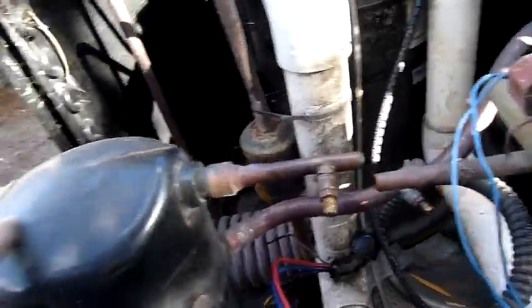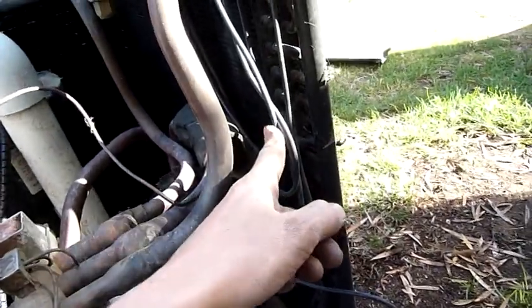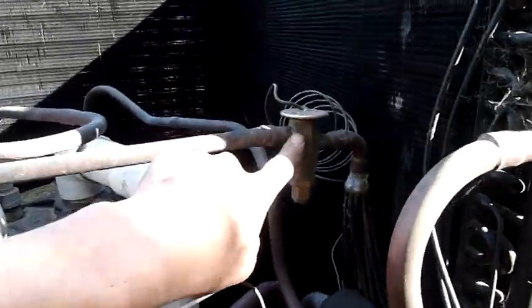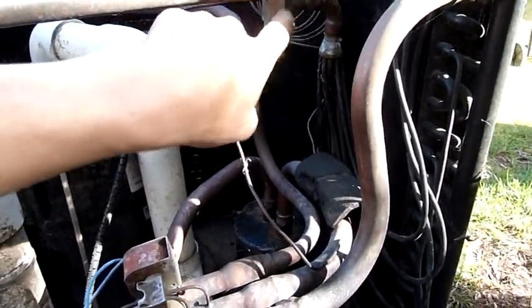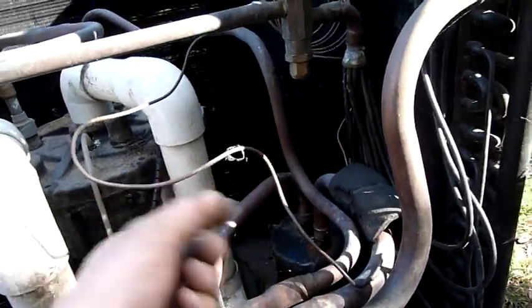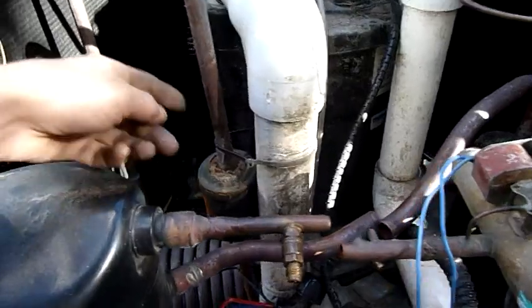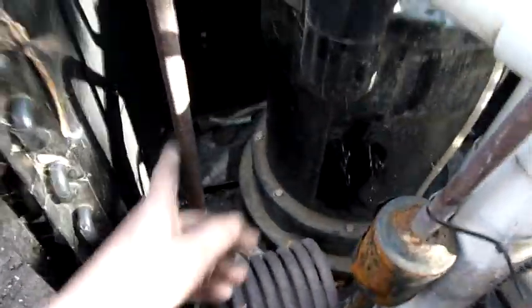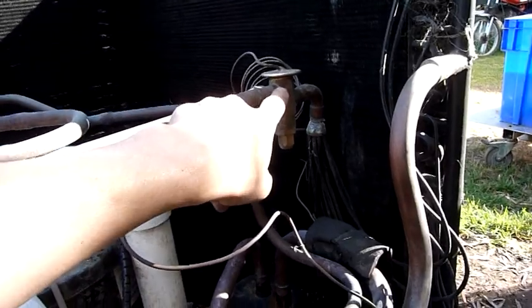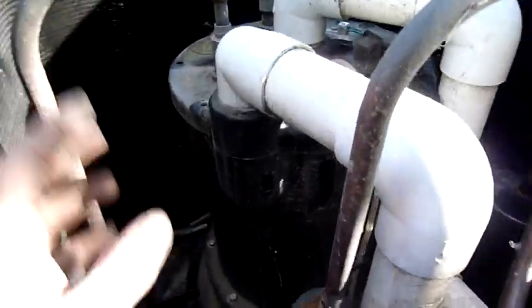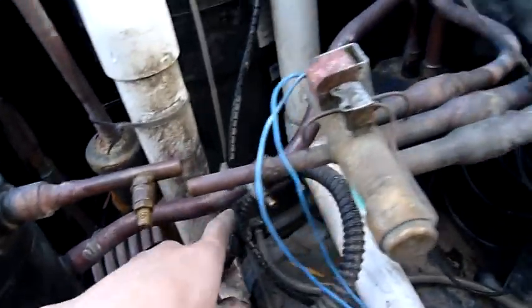You've got high pressure refrigerant coming out of the compressor, going through the condenser coil, exchanging all the heat. Heat gets blown off by the air from the fan, or drawn out, I think it gets drawn out through the top. Liquid refrigerant, which is condensed through the coil, comes through here, metered by the thermal expansion valve, which is regulated by suction line temperature and can dump liquid to suction line if needed. Goes through this coil and into the chiller drum, where it starts to evaporate as it comes through the TXV. As it's evaporating, it's absorbing heat from water in here, and then returns to the system as a vapor back down through here.